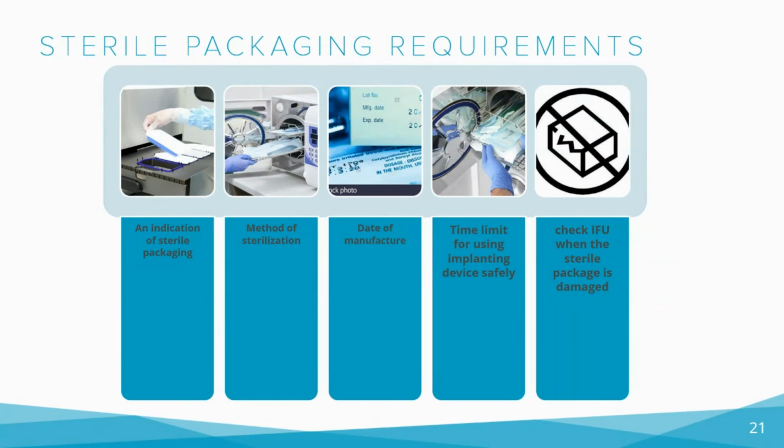According to the regulation, medical devices that are intended to be sterile must be labeled with a specific indication that conveys the following information. They are that the device is sterile, the method of sterilization used, and the date of sterilization. This indication must be clearly visible and legible on the device or its packaging, and it must be placed in a prominent position so that it is easily visible to the user. The indication must be provided in the official language or languages of the country or countries where the device is being marketed.